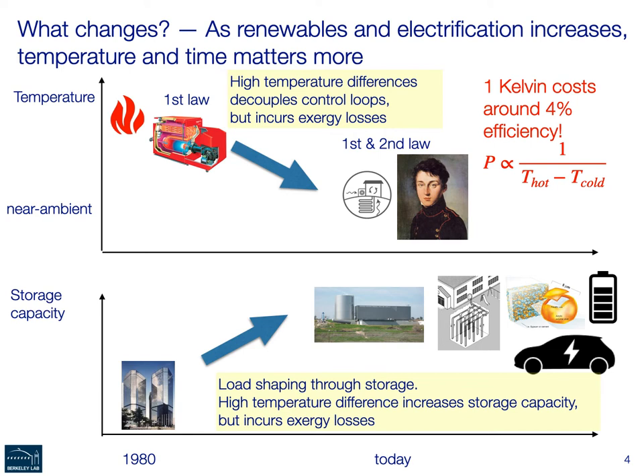At the same time as we want to reduce this temperature difference for efficiency reasons, we start coupling control loops much more tightly with each other, creating a tight coupling between the generation side and the distribution side.